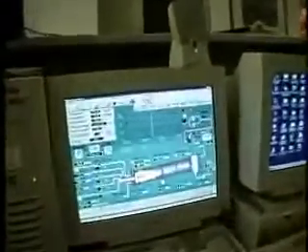We've had other controller guys come in here before and try and set things up, and it seemed that, you know, as long as everything was really, really perfect, it would run perfect. But as soon as we had an upset before, the controller would lose it. But this one seems to have, it catches all the problems. It seems to catch little upsets. It catches blips in fuel flow. It runs really, really well.